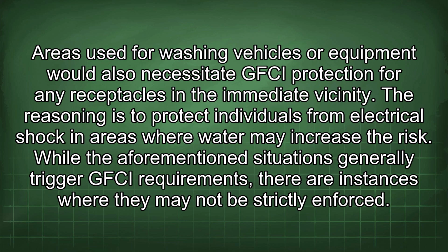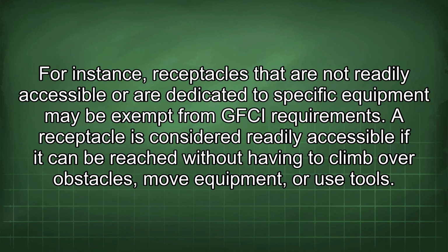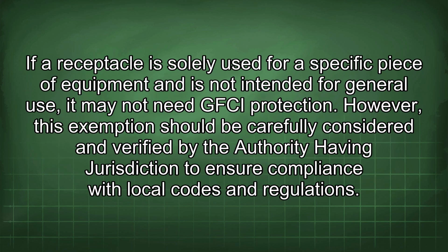While the aforementioned situations generally trigger GFCI requirements, there are instances where they may not be strictly enforced. For instance, receptacles that are not readily accessible or are dedicated to specific equipment may be exempt from GFCI requirements. A receptacle is considered readily accessible if it can be reached without having to climb over obstacles, move equipment, or use tools. If a receptacle is solely used for a specific piece of equipment and is not intended for general use, it may not need GFCI protection. However, this exemption should be carefully considered and verified by the authority having jurisdiction to ensure compliance with local codes and regulations.